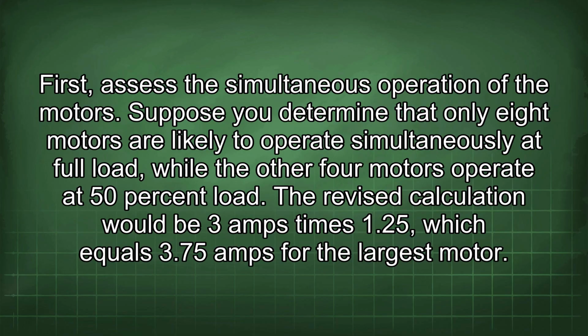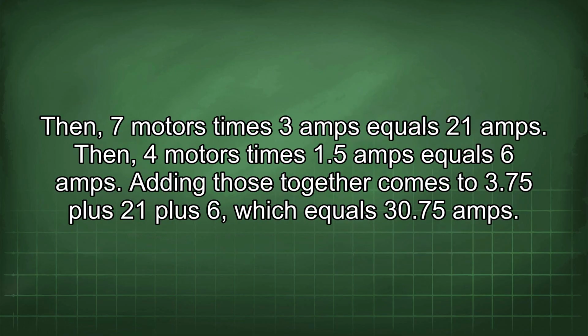First, assess the simultaneous operation of the motors. Suppose you determine that only 8 motors are likely to operate simultaneously at full load, while the other 4 motors operate at 50% load. The revised calculation would be 3 amps times 1.25, which equals 3.75 amps for the largest motor. Then, 7 motors times 3 amps equals 21 amps. Then 4 motors times 1.5 amps equals 6 amps. Adding those together comes to 3.75 plus 21 plus 6, which equals 30.75 amps.